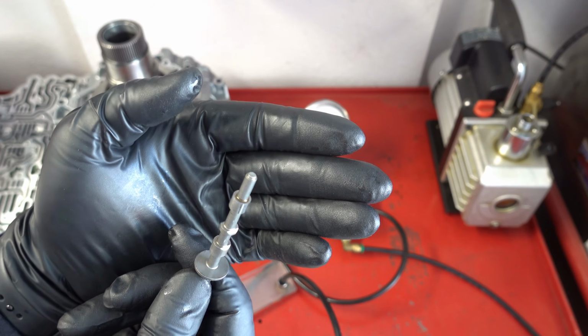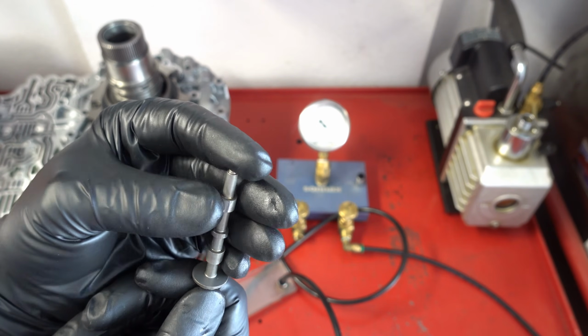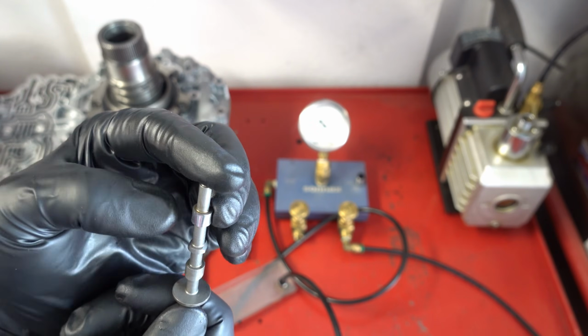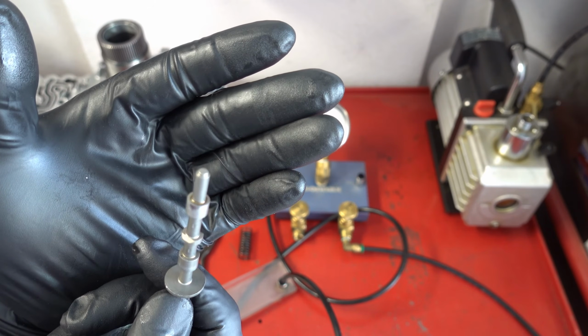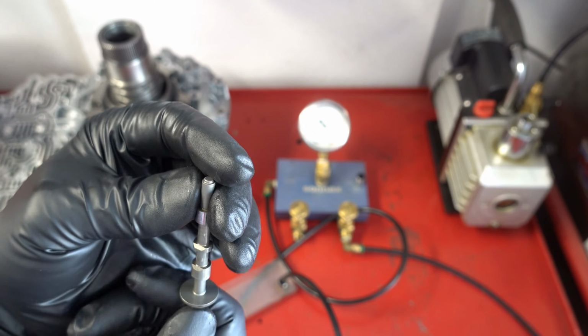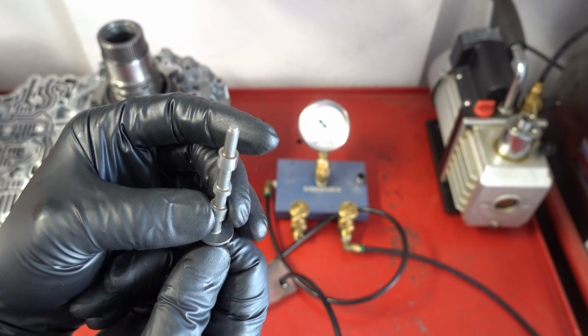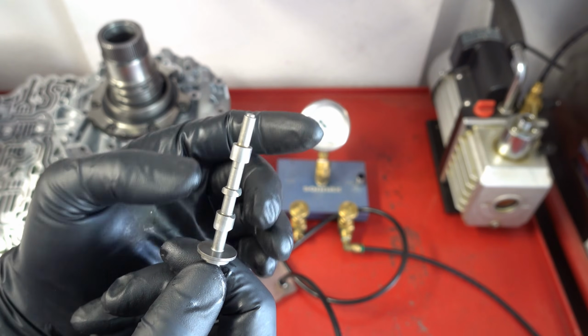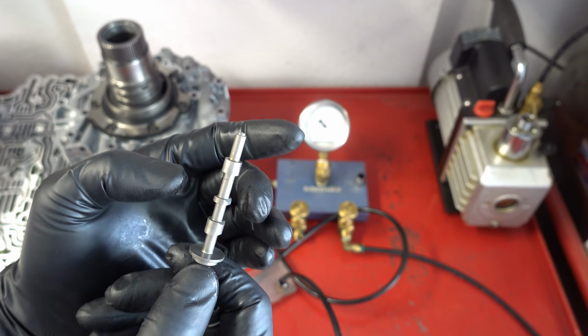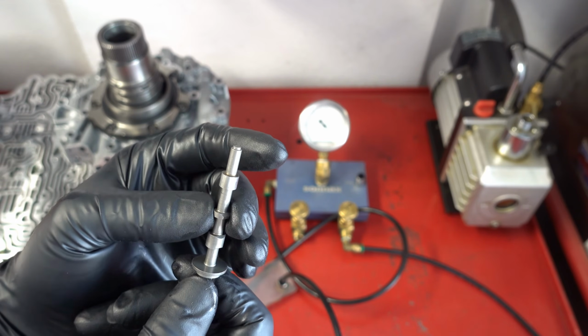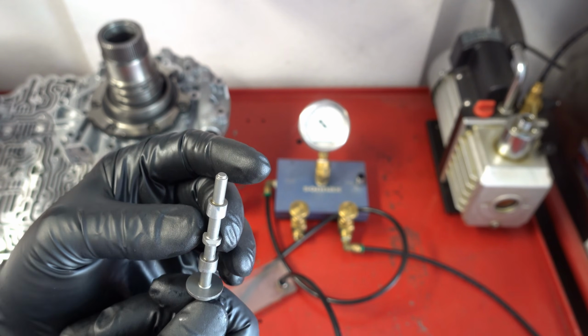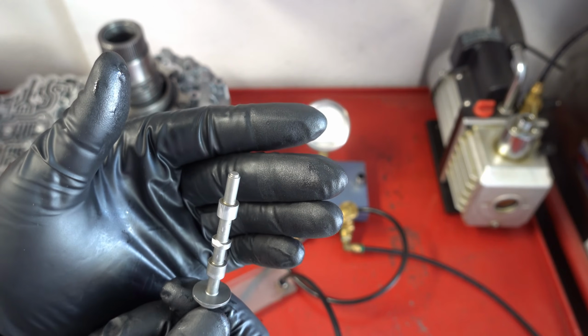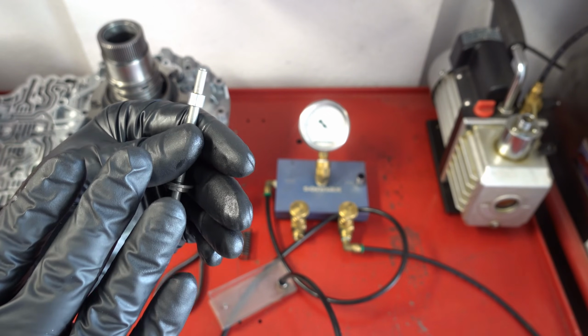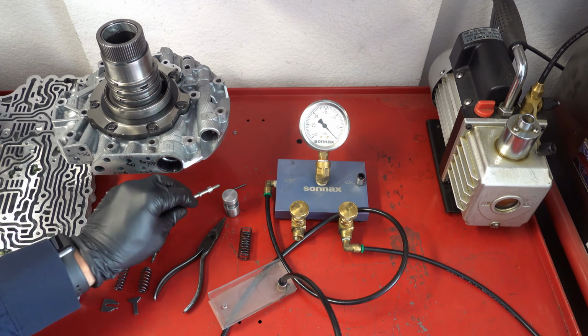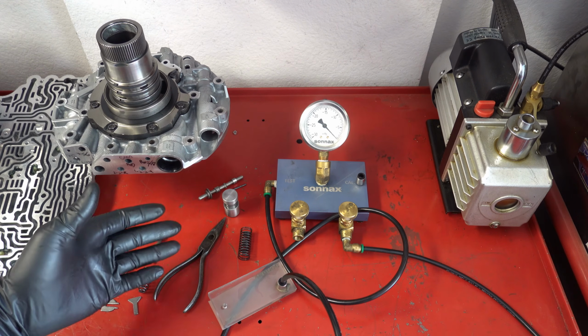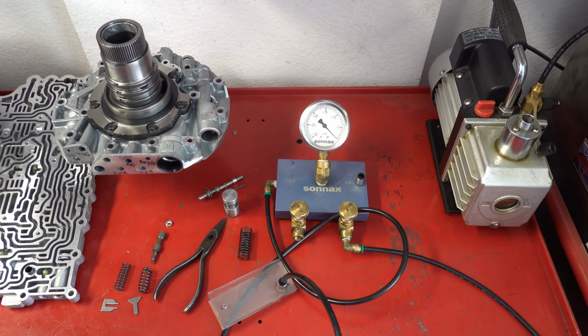If you note the wear here, you see it's pretty aggressive — this is very common, and that's why I wasn't holding any vacuum. This spool's fine, the outboard-most spool before the front of the valve is fine, and this intermediate spool is also okay. But the inboard spool looks like crap. It's not the worst I've seen by far, but it's no good here, and this testing exposed that.